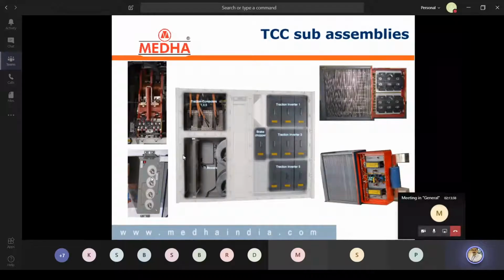So here we can find each and every IGBT is placed on top of one heat sink, and it's a heat pipe technology. So here we can find copper pipes. These pipes all extend from this end to this end with fins. Okay, and these modules are placed with gravity, that is, at a 10 degree inclination angle. So that is called gravity control technology.